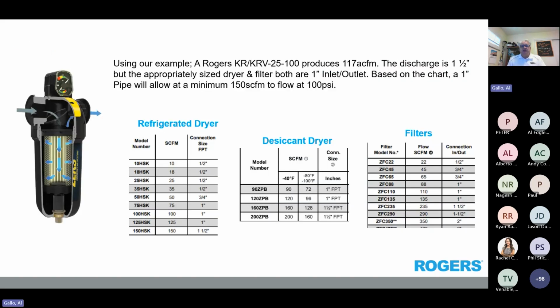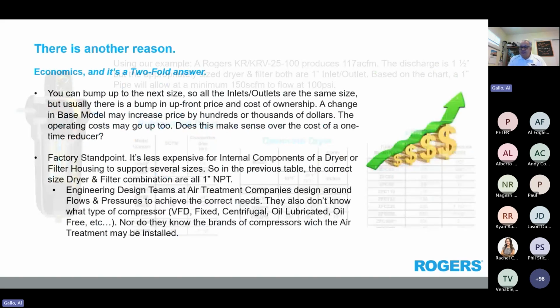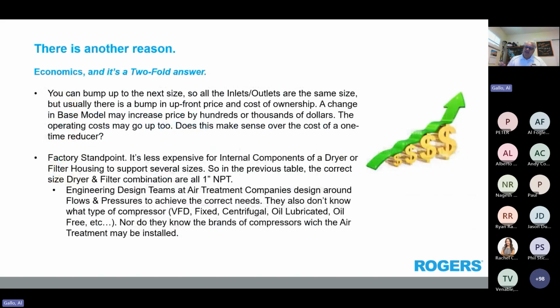Now, the question comes up, on the refrigerated dryer, the appropriate one for that KRV 25100 would be a 125 HSK refrigerated dryer, which is 1 inch. Could we jump up to the 150? Absolutely, you could jump up to the 150. There's a couple things to keep in mind if you decide to do that, and that's the economics of it. As you jump up in size, just to make all the piping work, you may also be increasing additional costs that you don't necessarily need to do.